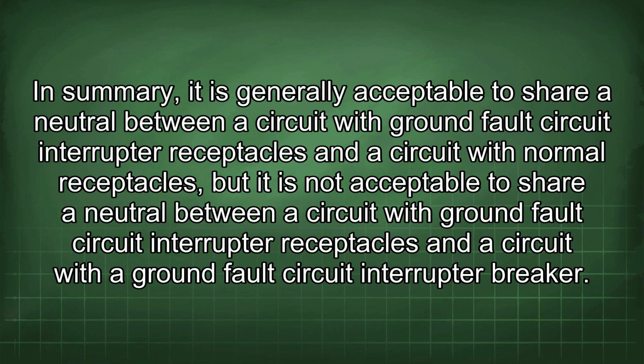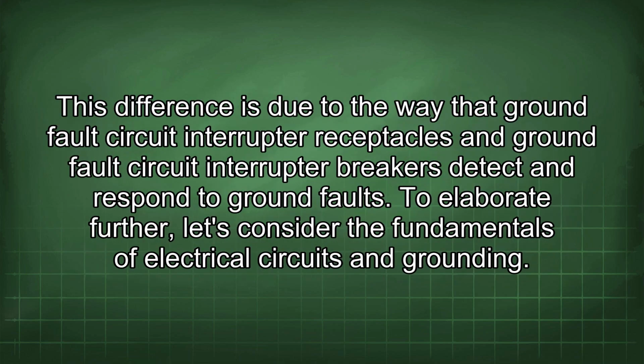In summary, it is generally acceptable to share a neutral between a circuit with ground fault circuit interrupter receptacles and a circuit with normal receptacles, but it is not acceptable to share a neutral between a circuit with ground fault circuit interrupter receptacles and a circuit with a ground fault circuit interrupter breaker. This difference is due to the way that ground fault circuit interrupter receptacles and ground fault circuit interrupter breakers detect and respond to ground faults.